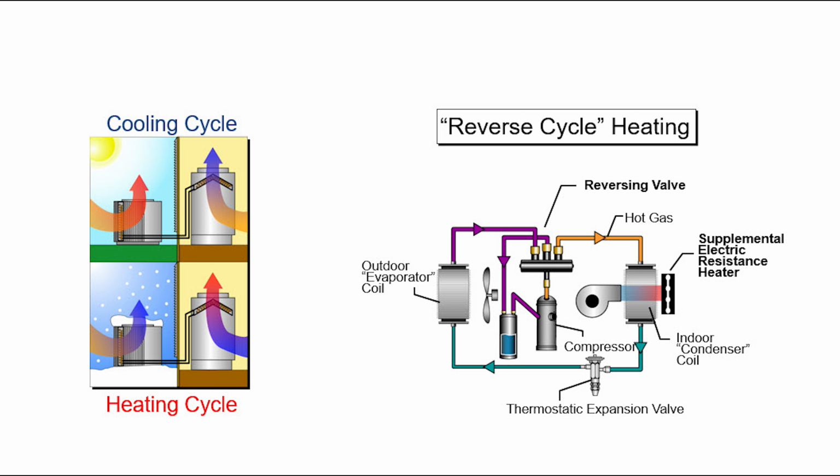That's exactly what a heat pump is going to do, except I'm not going to physically move the two pieces. Instead, there's a reversing valve in there, and that reversing valve is going to flip, and instead hot gas will leave the compressor, and instead of going to the outdoor coil, the hot gas will go to the indoor coil. And the two coils just switch jobs. There's one extra moving part in a heat pump, and that's the reversing valve.